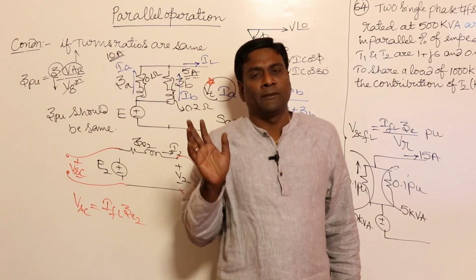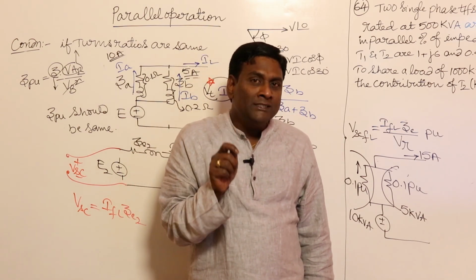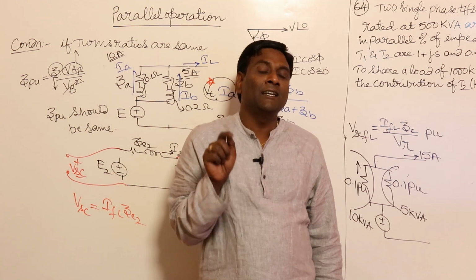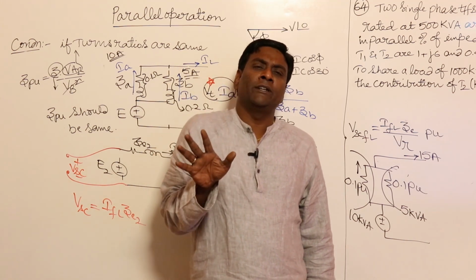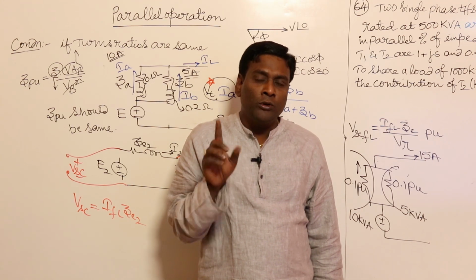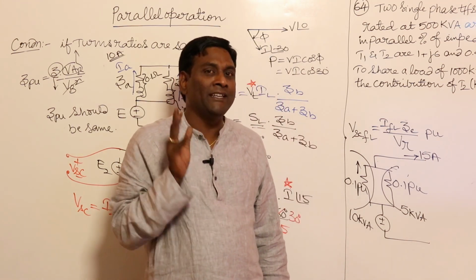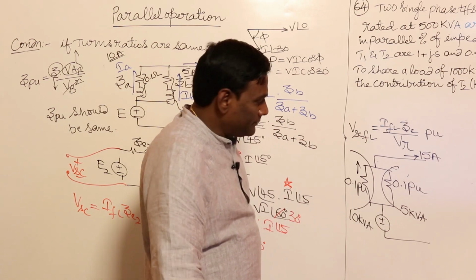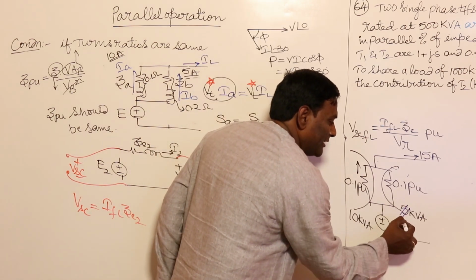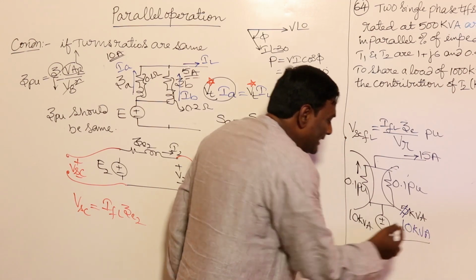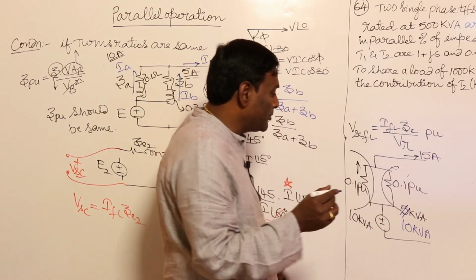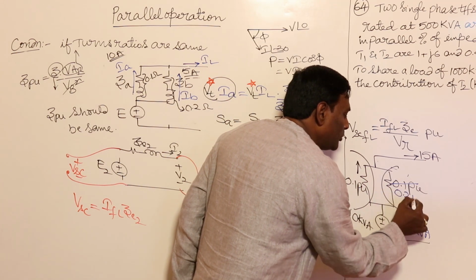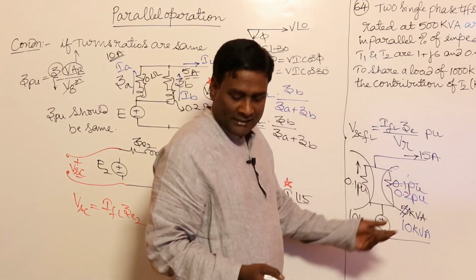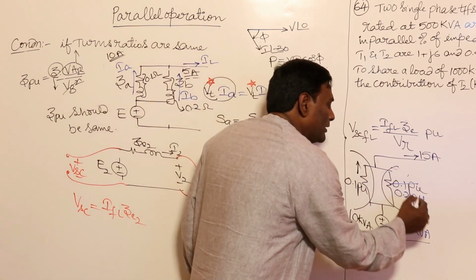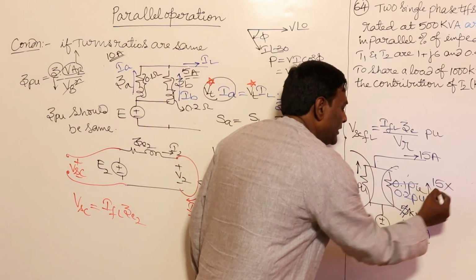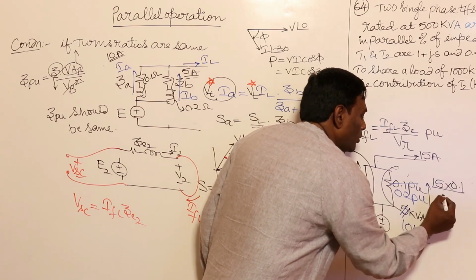So remember one thing. In calculating load shared by individual transformers, I repeat, in calculating load shared by individual transformers, all per units should be referred to a common base, a common kVA. So for example, if you convert this into 10 kVA, by considering 10 kVA as base for both, under that condition it will become 0.2 per unit. For 5 kVA, 0.1; for 10 kVA, 0.2. So now if you calculate the current flowing through this, it is total current 15 into the other impedance 0.1, divided by the total impedance 0.3.